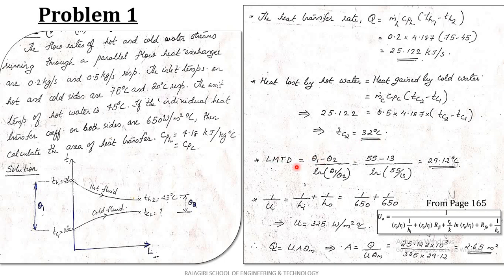Now calculate the LMTD: θ_m = (θ1 − θ2) / ln(θ1/θ2). Here θ1 = 75 − 20 = 55, and θ2 = 45 − 32 = 13. So LMTD = (55 − 13) / ln(55/13) = 29.12°C for the given parallel flow heat exchanger.